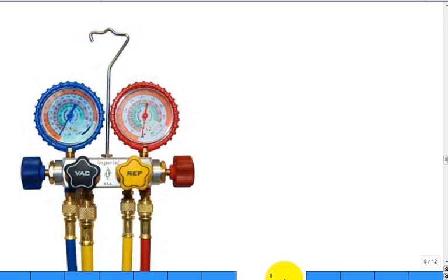Right? Did anybody see a technician come out with this type of gauge, hook it up? There's a lot of hoses they can hook up to the refrigerant system, but essentially one is colored red, one is colored blue. I wonder why. One for hot, one for cold. Which one is the condenser? The high pressure side, the hot side? What is the evaporator? The low pressure side, the cold side? And so basically this dial right here, you could see what is the pressure in the condenser and you can read off the pressure in the evaporator.